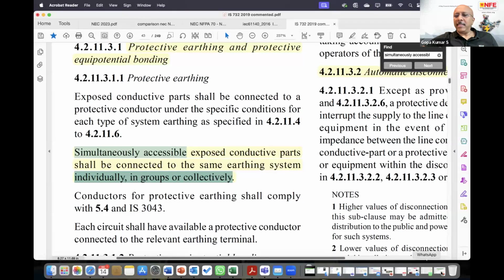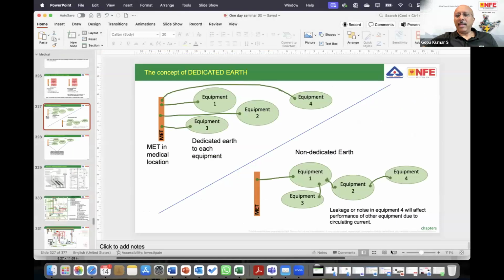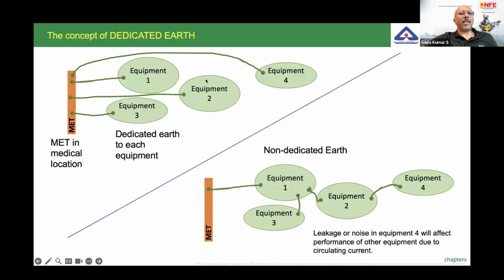A lot of times, this is a big confusion in our country. For example, just as a concept, I am putting this picture. You have the common bus bar. All these equipment 1, 2, 3, 4 are class 1 equipment. The standard uses the word individually earthed, whereas colloquially we use the word dedicated earth.